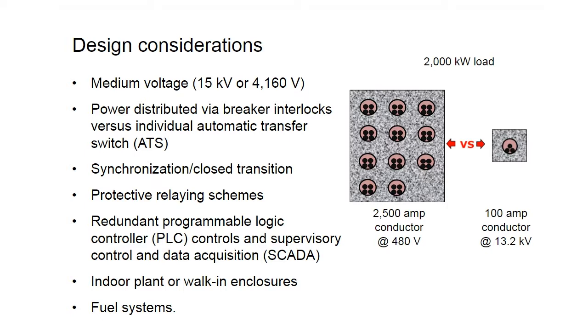Another issue, as Scott had mentioned, is a lot of ATS functions with a hospital and some things like that. Because of the amounts of load and because you're picking up the entire building, you tend to see a lot more breaker interlocks versus ATSs, where the main, the generator and the utility breaker create that ATS. Also with data centers, the cooling becomes an issue as you're trying to cool the space. Going to generator and then coming back, a lot of times you want to do a close transition, so synchronizing with utility so you don't have an outage when you go back from generator to utility. With all those schemes, obviously you have a protective relaying scheme, differential protection, things of that nature that you need to address. And again, because it's basically a smart system, you'll have PLC controls, and you'll make sure you have redundancies in the PLCs and so forth, so you don't lose one component and lose the entire system.